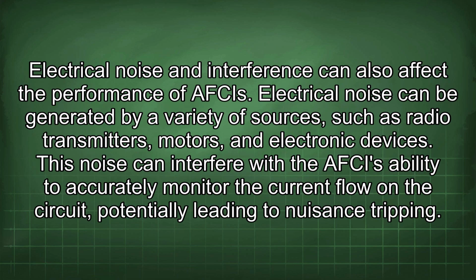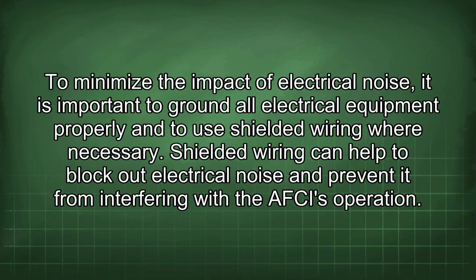Electrical noise and interference can also affect the performance of AFCIs. Electrical noise can be generated by a variety of sources such as radio transmitters, motors, and electronic devices. This noise can interfere with the AFCI's ability to accurately monitor the current flow on the circuit, potentially leading to nuisance tripping. To minimize the impact of electrical noise, it is important to ground all electrical equipment properly and to use shielded wiring where necessary. Shielded wiring can help to block out electrical noise and prevent it from interfering with the AFCI's operation.